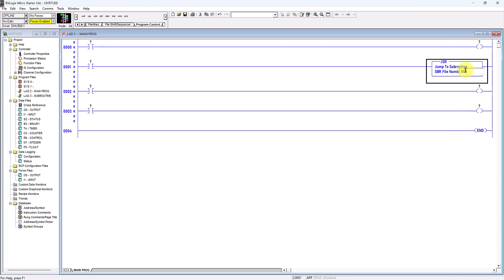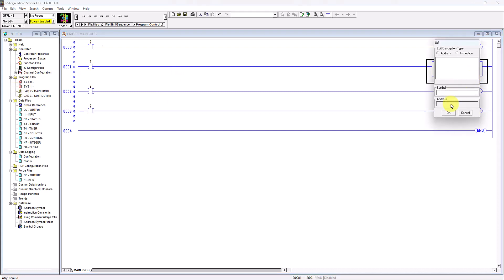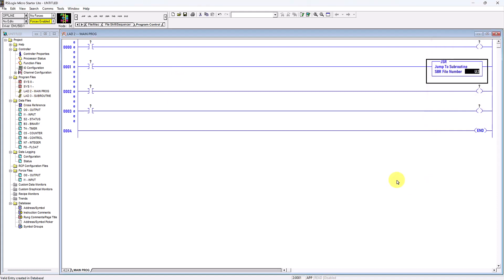I need to give the JSR instruction a subroutine file number. I will double-click and type U:3. U stands for subroutine, and the 3 refers to file number 3. The colon is followed by the file number.